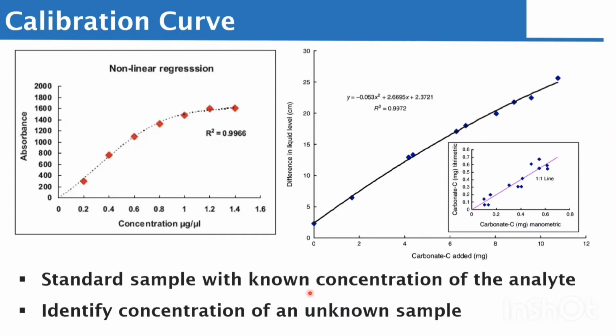So when you say calibration plasma, when you say calibration blood, as the case may be, it's a known concentration sample. So we know what is in it. So we can then use it because it's coming from the manufacturer. We can then use it to calibrate our analyzer to give it the range of how sensitive it can be in determining abnormal low, normal, or abnormal high. So what it then means is that this calibration curve can help to identify the concentration of an unknown sample. So when we've used a known concentration like our calibration plasma, calibration sample, and done calibration, once we've accepted that calibration curve, the analyzer, using that curve, can then identify the concentration of an unknown sample, which is the patient sample.